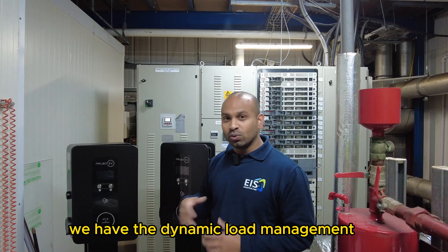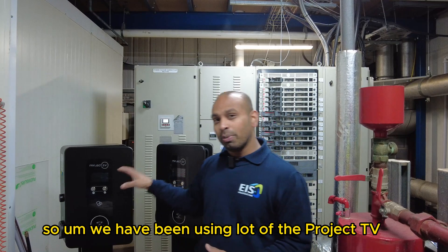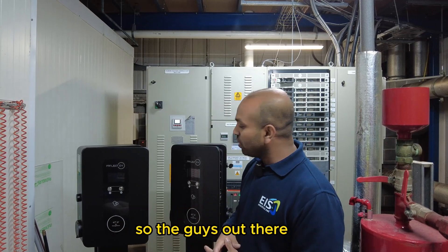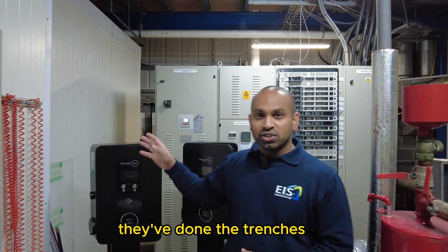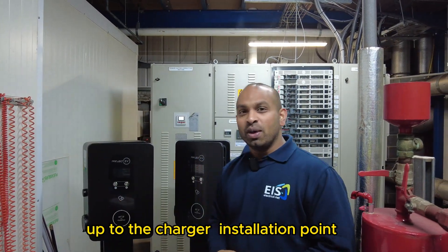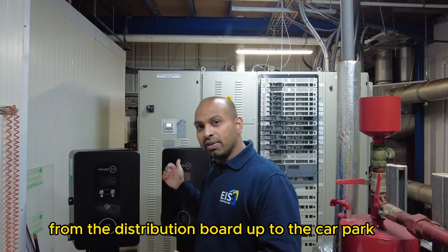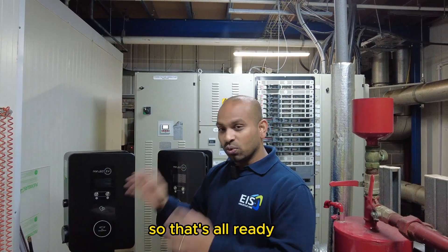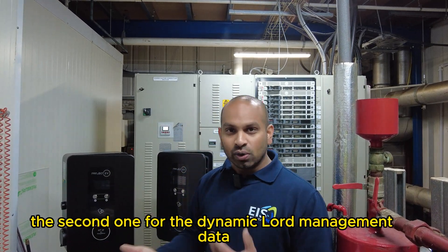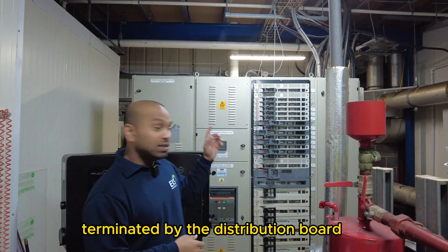There's loads of tech built in: PEN fault detection, dynamic load management, all the smart capabilities. We've been using a lot of Project EV domestic chargers in the last few years, but this time we went for the main commercial version. The guys have done the groundworks — the trenches are dug and the cables are laid. Because of the distance from the distribution board to the charge installation point, we had to run a 25mm five-core three-phase cable. We've also got CAT6 cabling for the data network and for the dynamic load management.